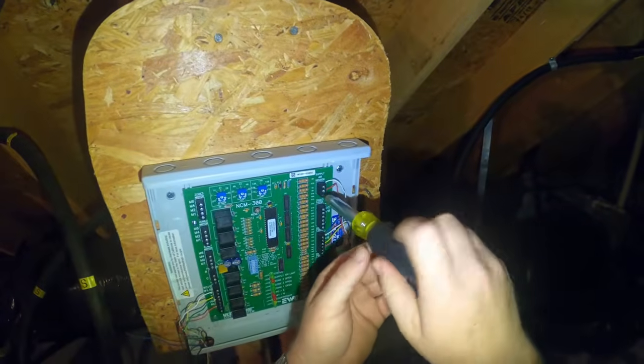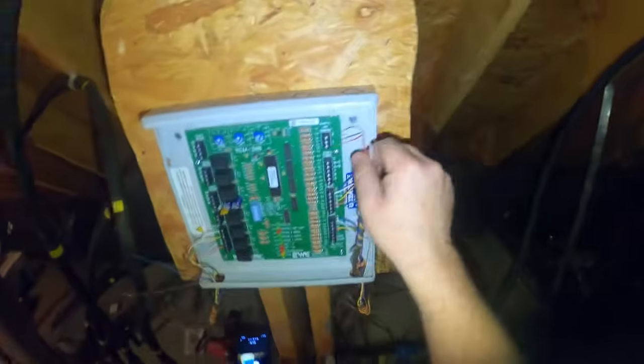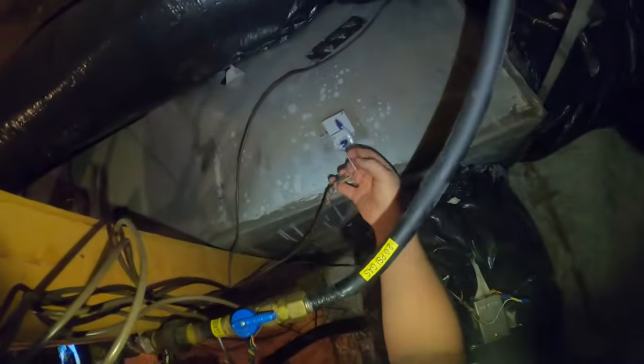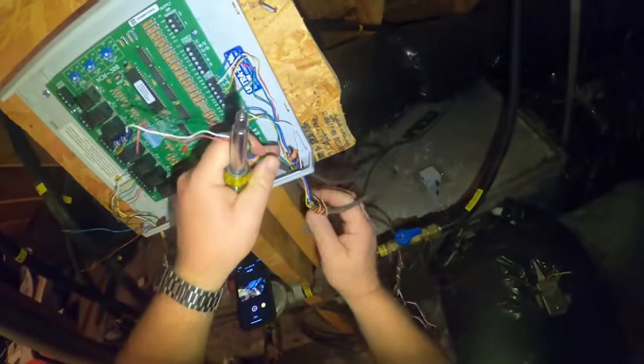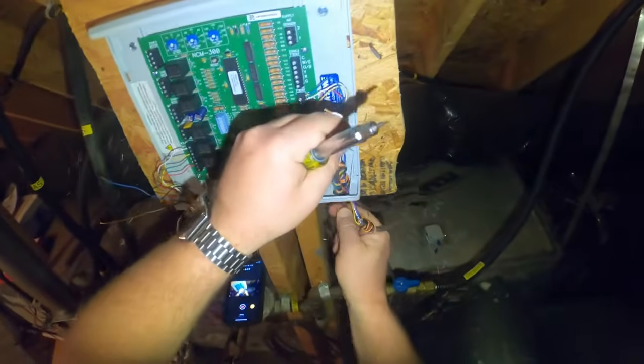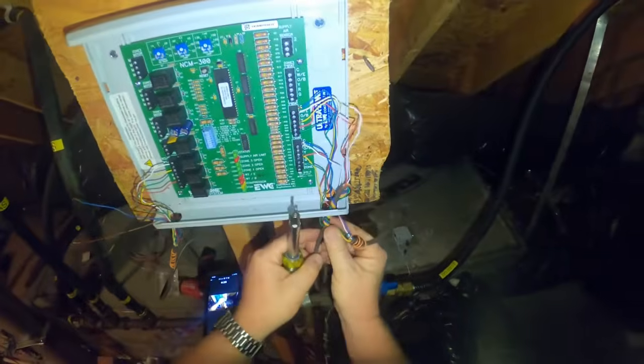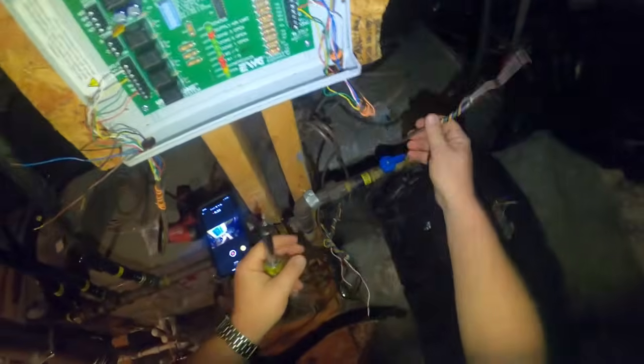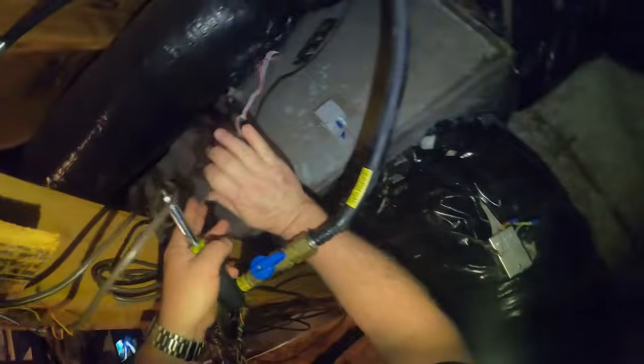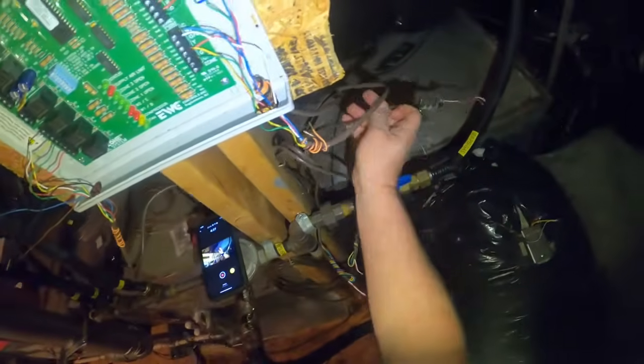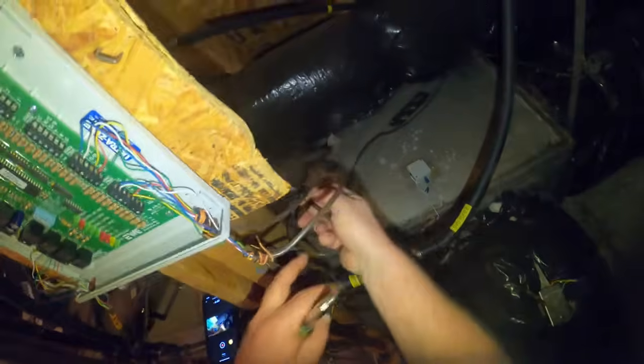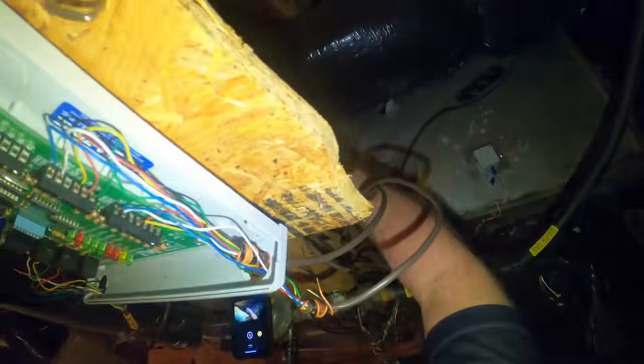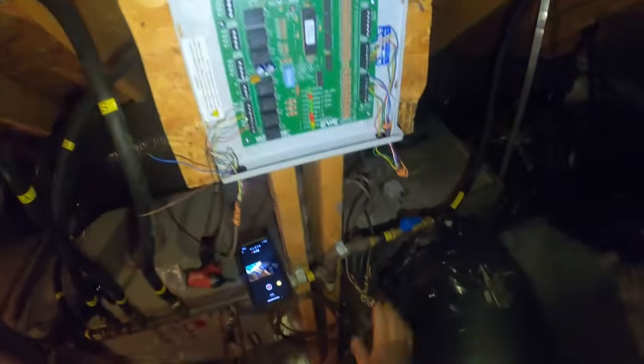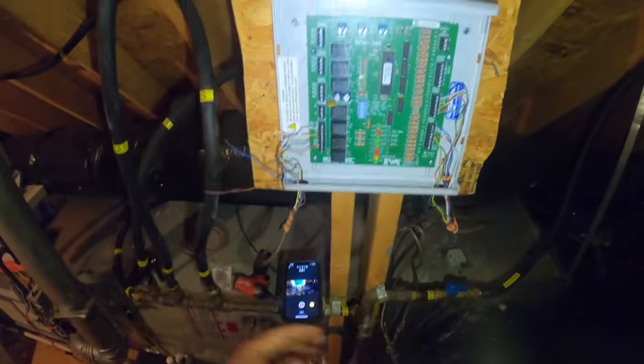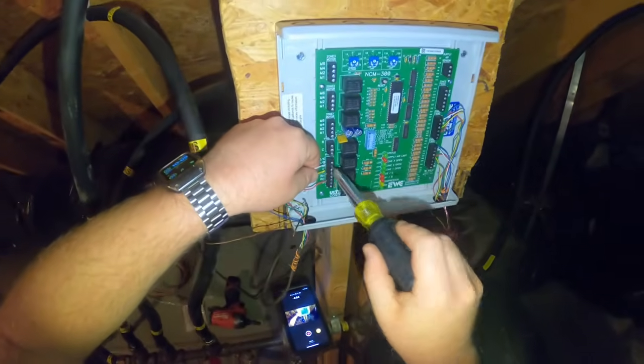So we have an air sensor connected here on this board, and it's going to go right there. If it's a 10K sensor, I should be able to reuse that with the Trane, or maybe not, I don't know, but we'll see. So I'm going to tuck my sensor back here so I know that that one goes to my sensor. And these two go to my zone motors. And now we've got our equipment right here.